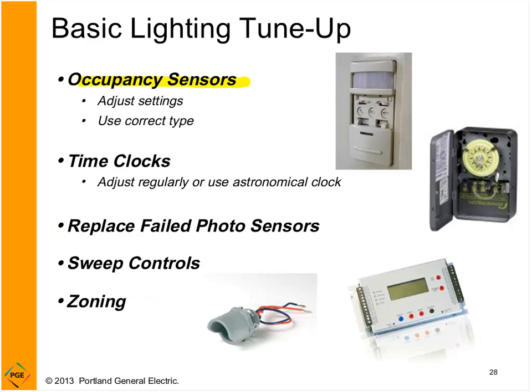Just because you have these installed doesn't mean you don't need to make adjustments to them. I've been into many buildings where the occupancy sensor in the conference room will turn lights on and off purely based on what's going on out in the hallway, not on what's going on in the room. If that's happening at your facility, look at where this sensor is pointing. You can often change the direction to make sure it's looking in the proper area to sense activity in the room in which the light is being controlled.